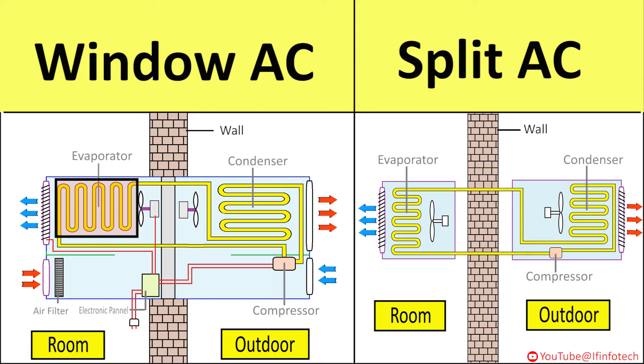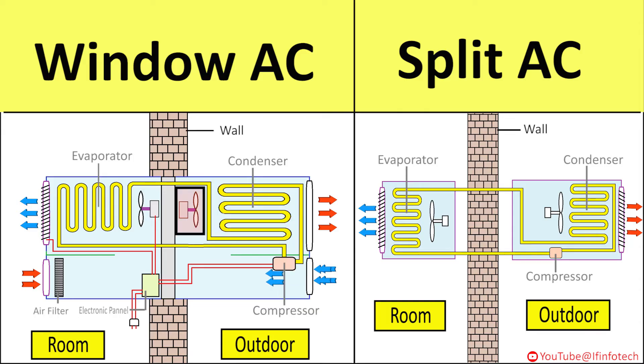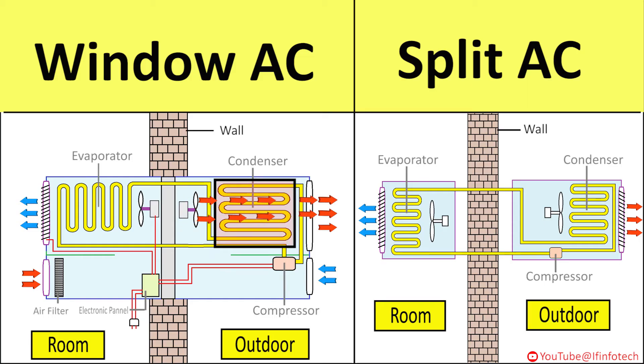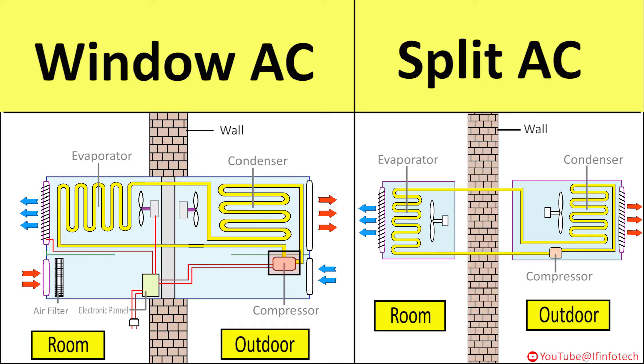Moisture present in the circulating air is removed and flows from the coil surface downward. The compressor and condenser are fitted such that the fan draws outside air from the lower portion of the outside unit, flows it over the condensing coil, and discharges it outside. While passing air over the coil, the condenser rejects heat to the air, and refrigerant vapor condenses into liquid form.